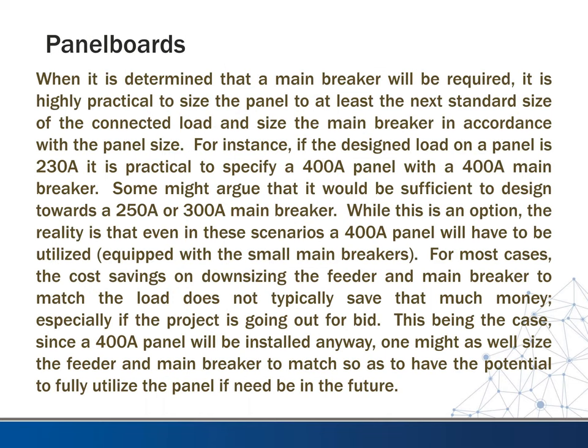So when it's determined that a main breaker will be required, it is highly practical to size the panel to at least the next standard size of the connected load and size the main breaker in accordance with the panel size. So for instance, if the design load on a panel is 230 amps, it's practical to specify a 400 amp panel with a 400 amp main breaker.